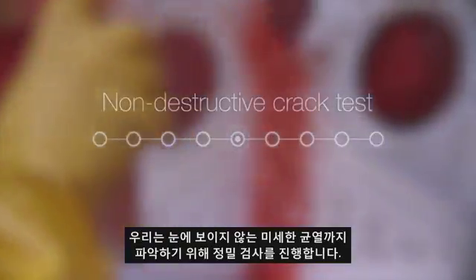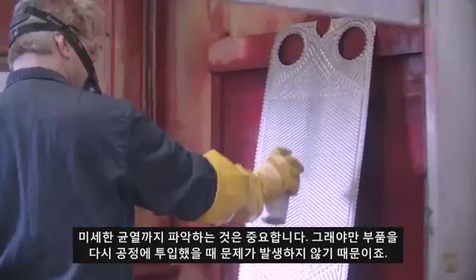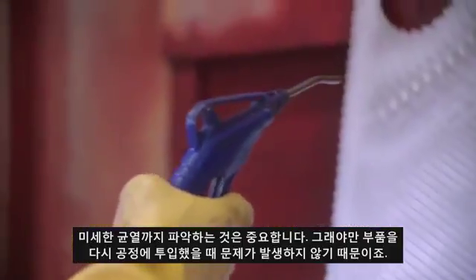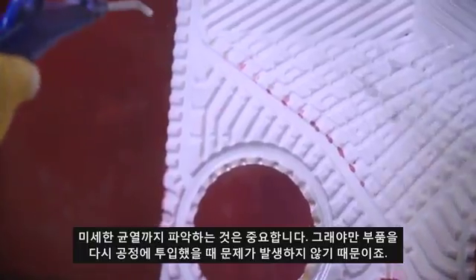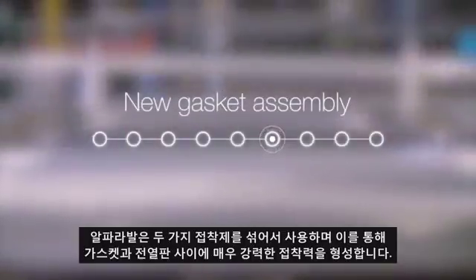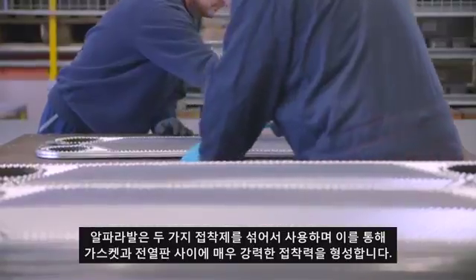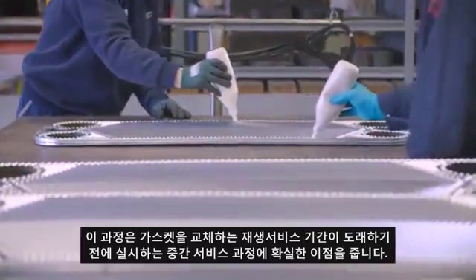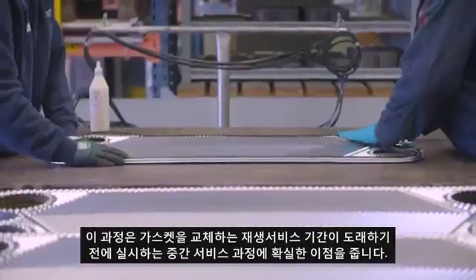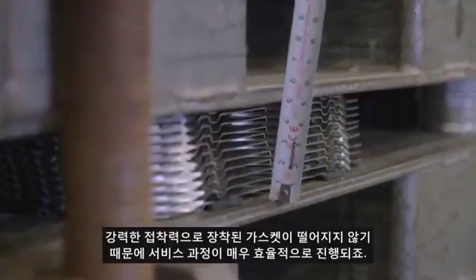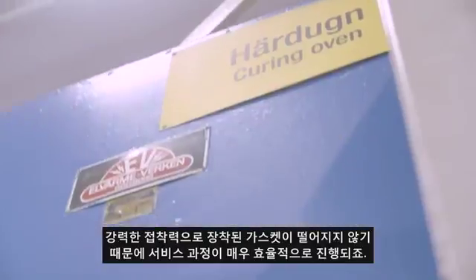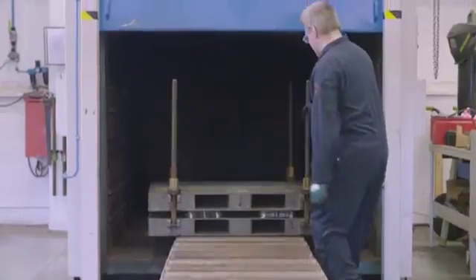We do a non-destructive crack test in order to identify cracks not even visible to the eye. And that's important because you want to identify those so you don't have any failures when you put the unit back in operation. We use a two-component cured glue to give a very strong bond between the gasket and the plate. That gives you the advantage when you do service in between reconditioning that the gaskets don't fall out and your cleaning processes will be more efficient.